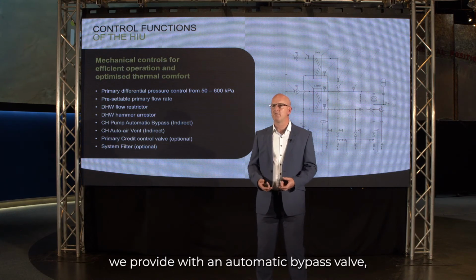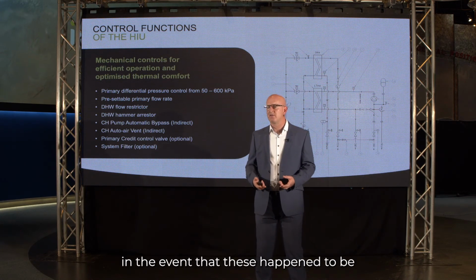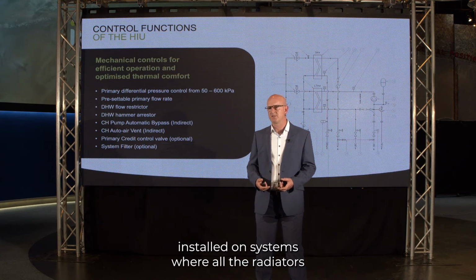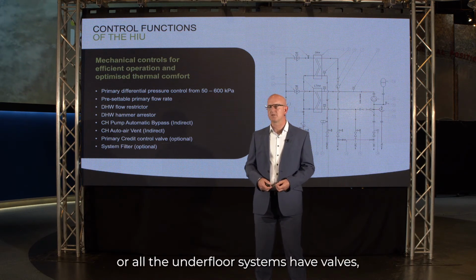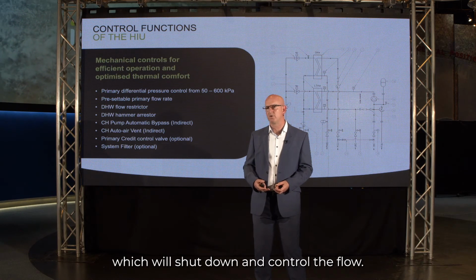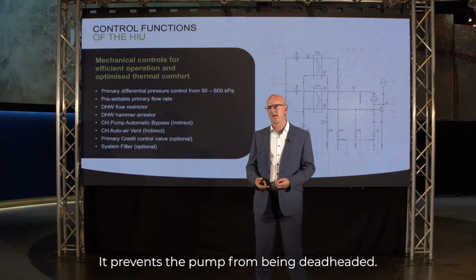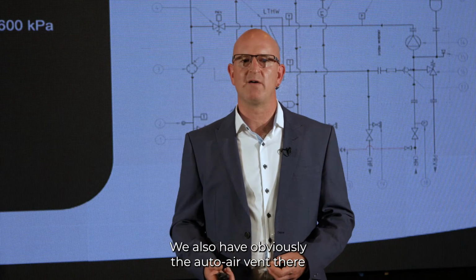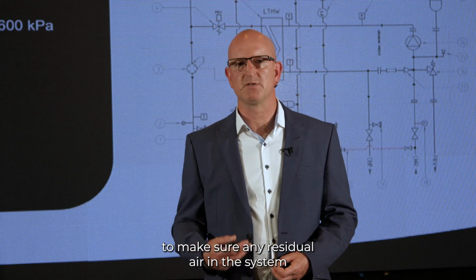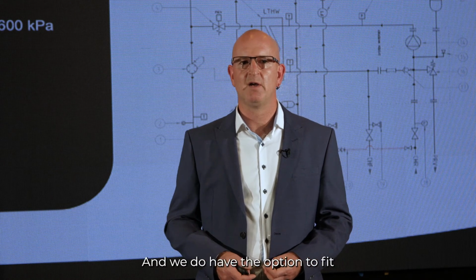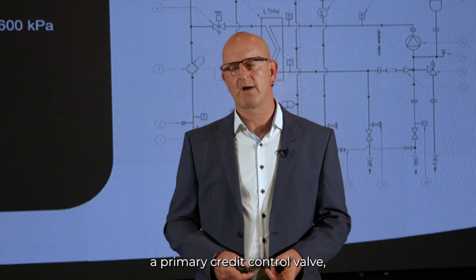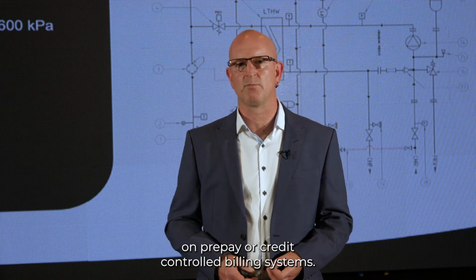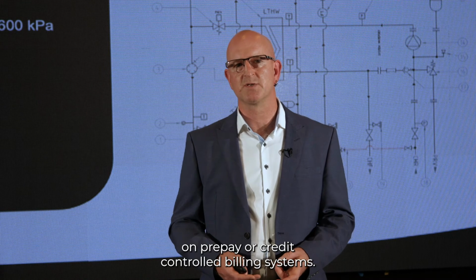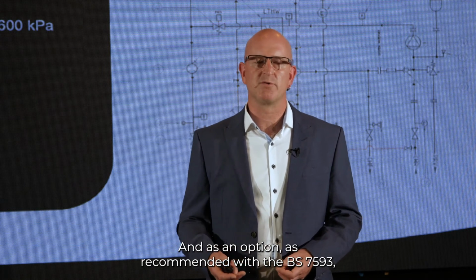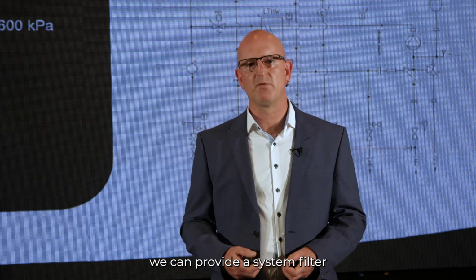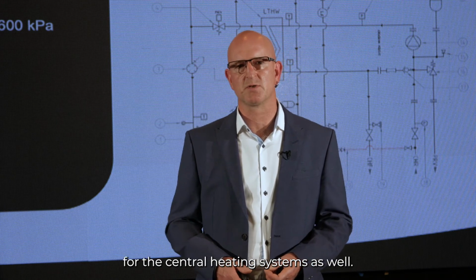The central heating pump we provide with an automatic bypass valve in the event that these happen to be installed on systems where all the radiators or all the underfloor systems have valves which will shut down and control flow. It prevents the pump from being deadheaded. We also have the auto air vent there to make sure any residual air in the system is bled out as it's circulated round. And we do have the option to fit a primary credit control valve where these systems are being used on prepay or credit controlled billing systems. And as an option, as recommended in BS 7593, we can provide a system filter for the central heating systems as well.